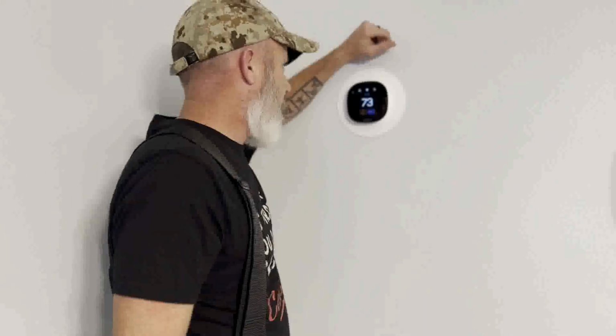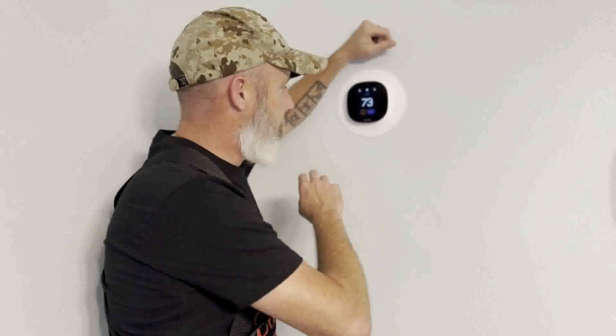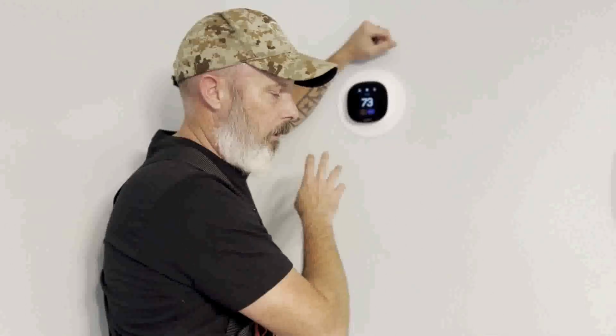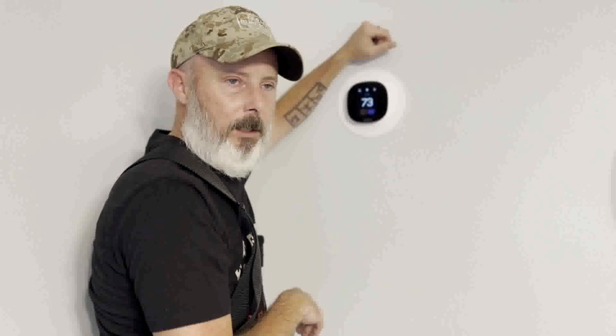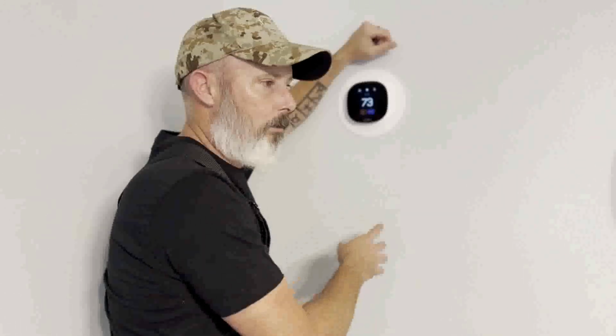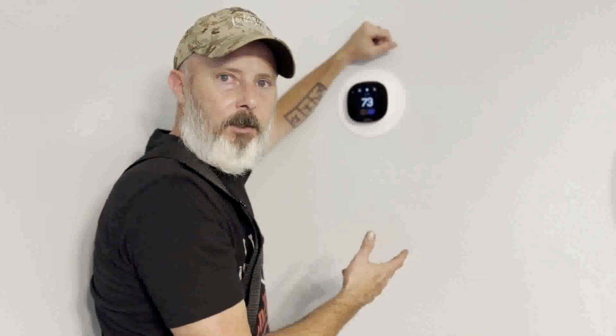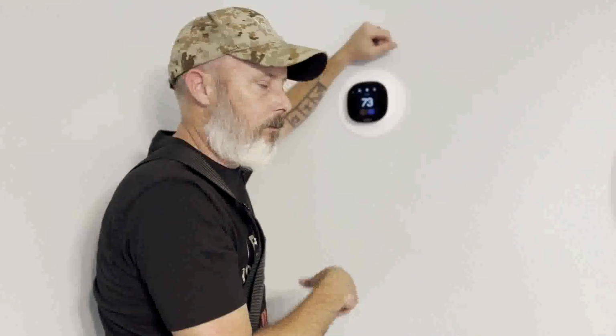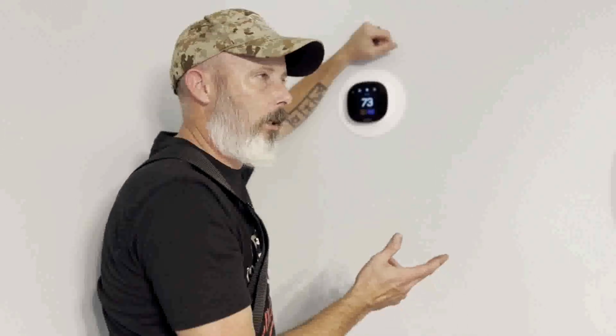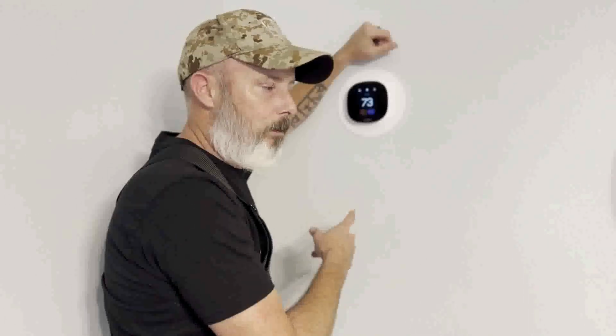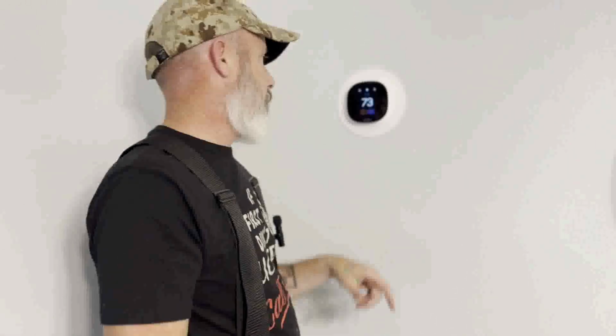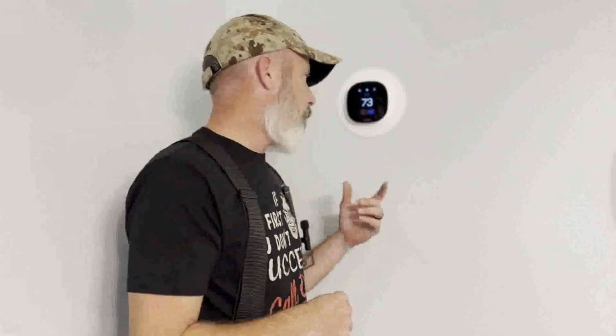All right, let's take a second to talk about the thermostat. The way I have the control set up is it uses just a regular thermostat. You know, some people you'll see they'll have 2 thermostats. One's for wood boiler heat, and the other thermostat is for whatever other heating system they got. So if it's propane or heat pump or natural gas or oil, whatever. A lot of people have 2 thermostats. This thermostat is set up for a heat pump. All I'm doing under the house is, if the water is hot enough, I'm basically intercepting the call for the heat pump.